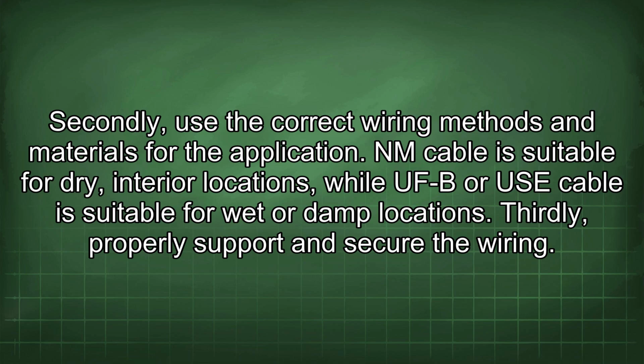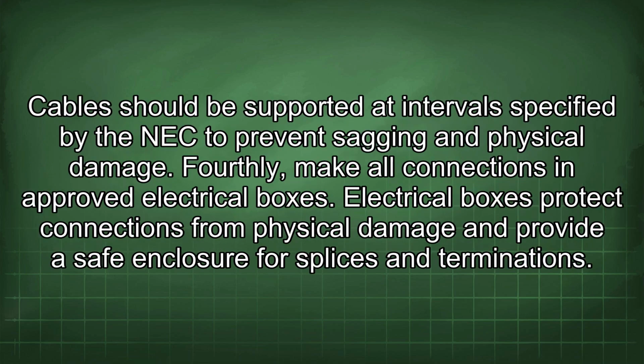Thirdly, properly support and secure the wiring. Cables should be supported at intervals specified by the NEC to prevent sagging and physical damage. Fourthly, make all connections in approved electrical boxes. Electrical boxes protect connections from physical damage and provide a safe enclosure for splices and terminations.